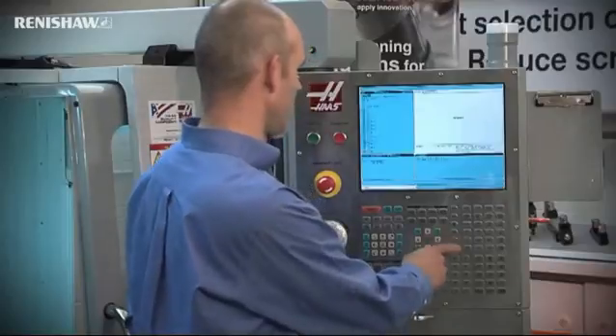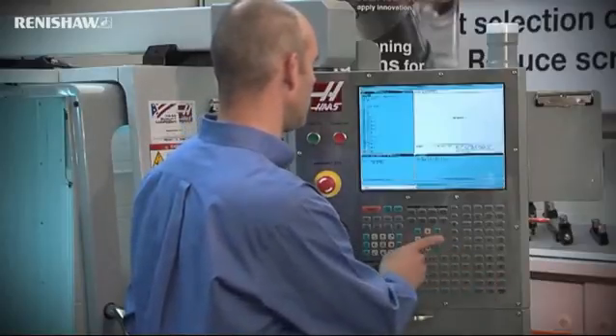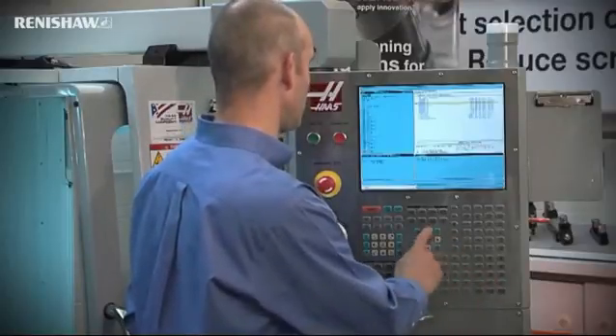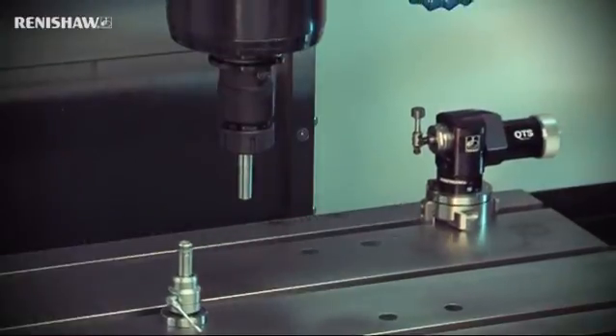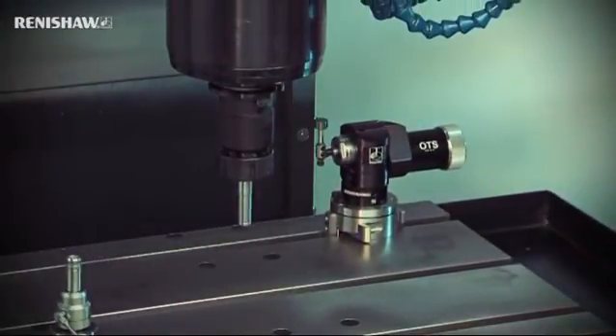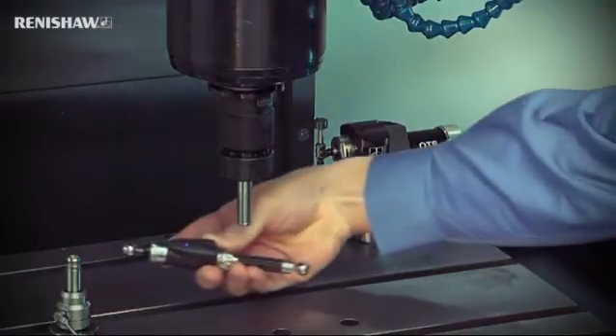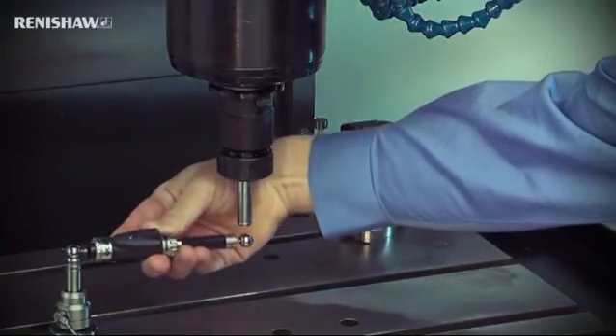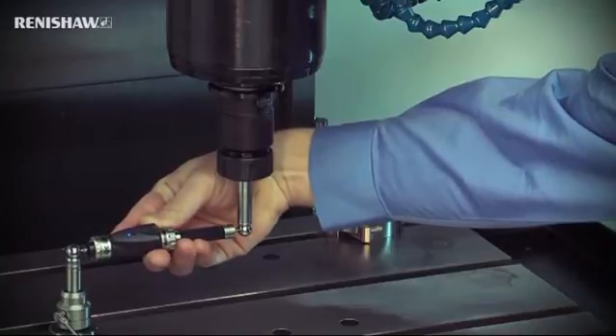If you have not already done so, you should now load and test the part program before you attach the ball bar. Once you are sure that the part program is working correctly, press cycle start to position the machine to the start point. The M00 command will cause the program to wait while you load the ball bar. Load the ball bar into the machine, taking care that the balls are firmly engaged with the magnetic cups.